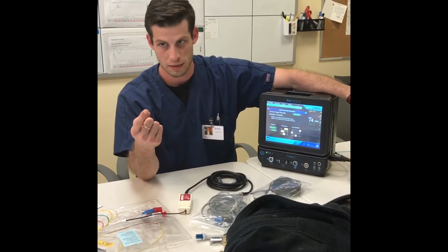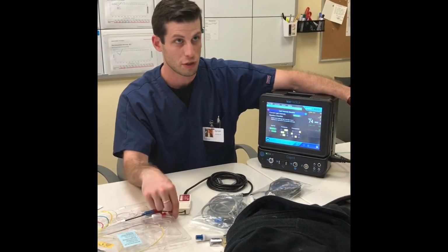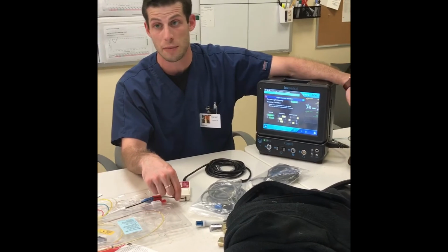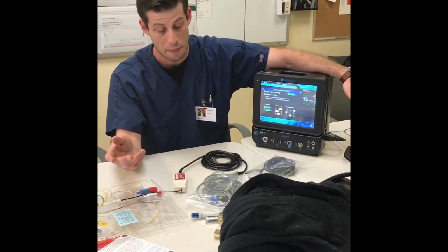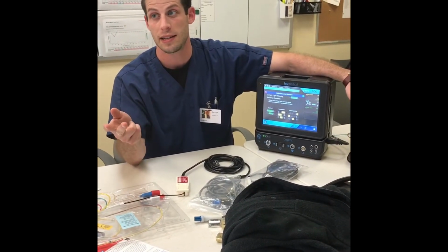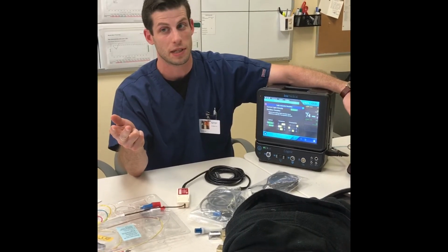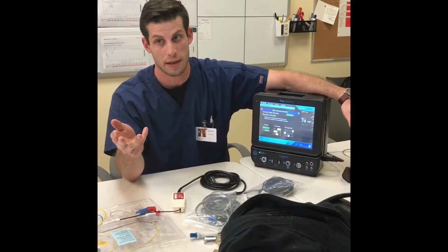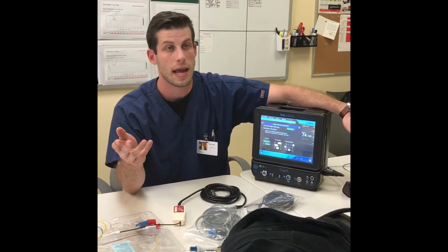You have a kink somewhere in this optical line, so you just maybe massage it out, or someone may have really damaged it, and you have to put in a new line, which we hope doesn't happen. There's a clot sitting at the end of the catheter blocking the fiber optics, or there's fibrin buildup at the end of the catheter blocking the optics. Happens with all of these.